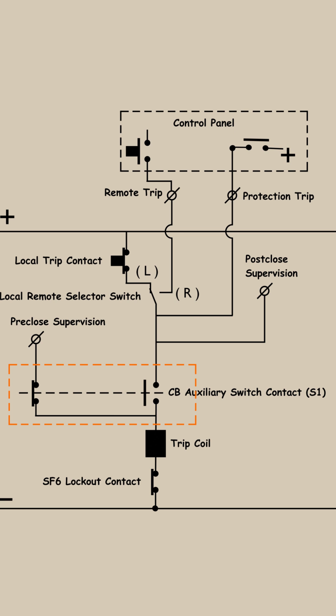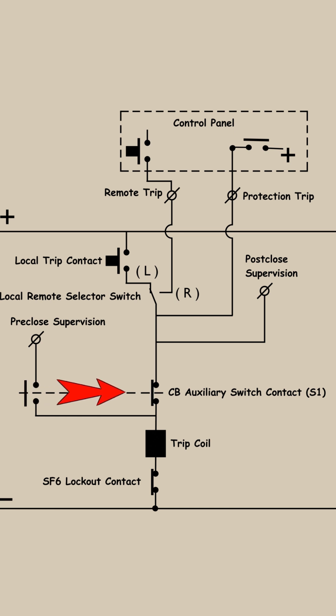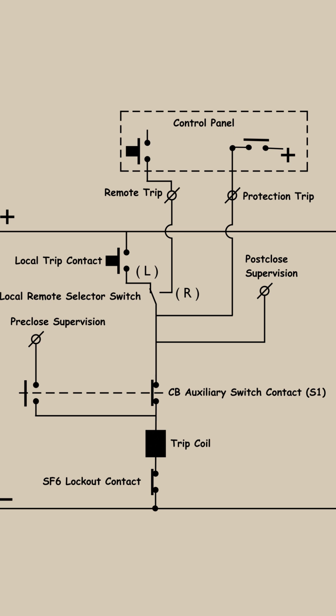From the tripping circuit, we can clearly see that there are two conditions to be fulfilled for tripping of the circuit breaker. One is that the circuit breaker must be in the closed position. If the circuit breaker is in the closed position, then only this auxiliary switch contact will also be in the closed position — this normally open (NO) contact of the auxiliary switch is in a closed condition. And if the pressure of the SF6 gas in the circuit breaker is above the lockout pressure, then the SF6 lockout contact will also be in the closed position.